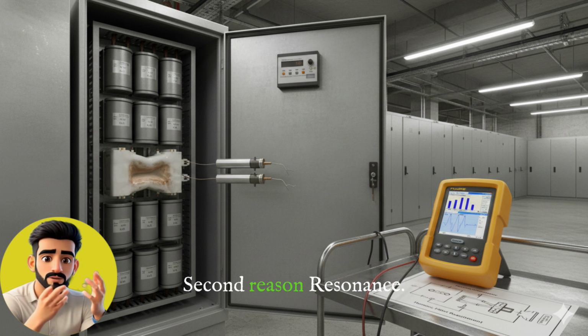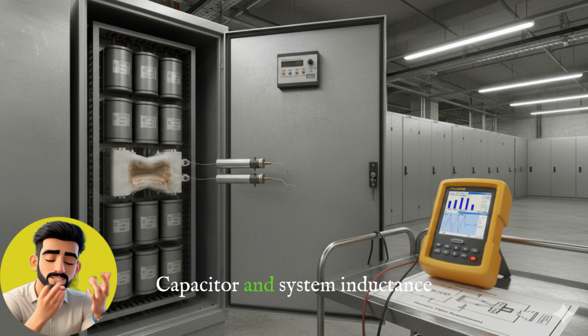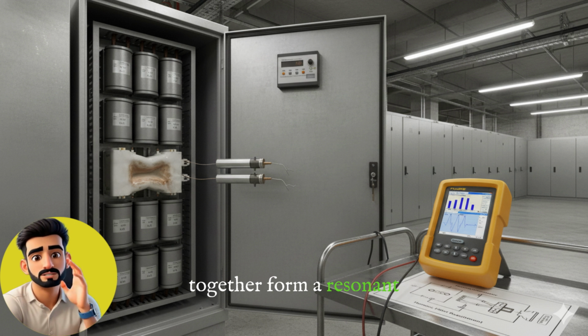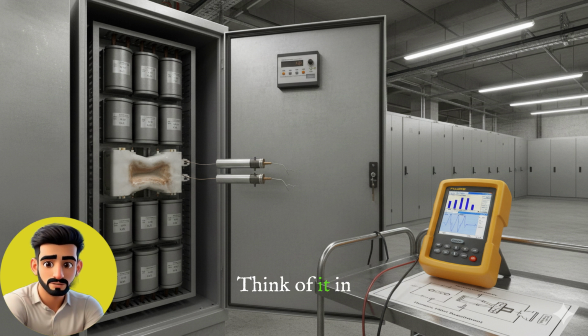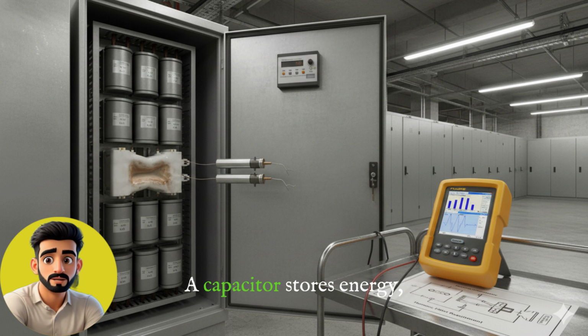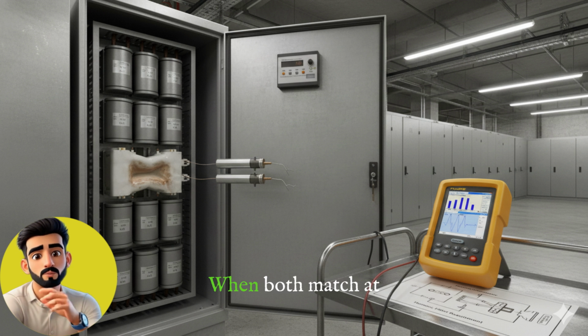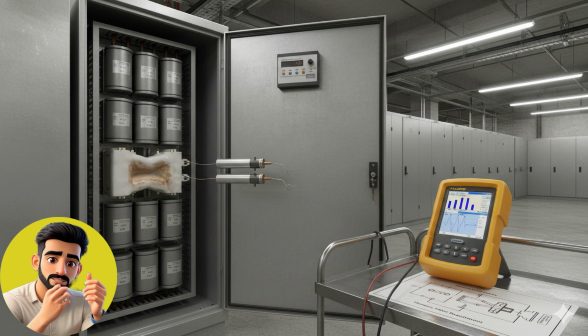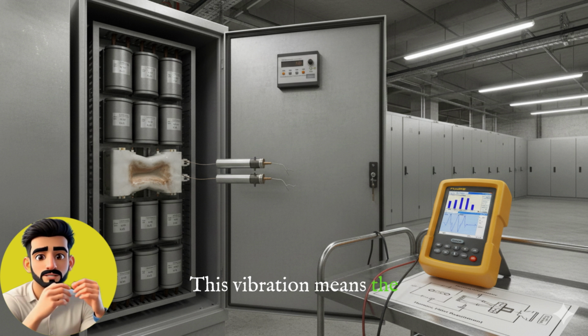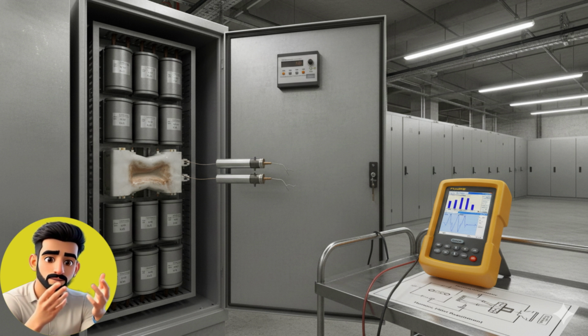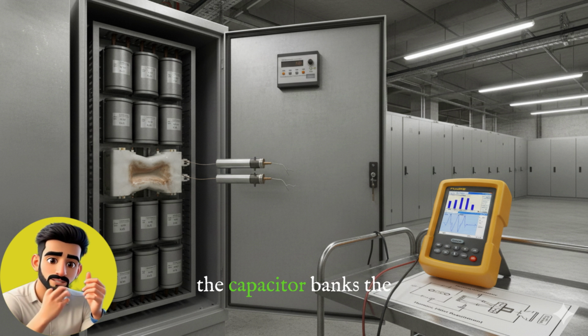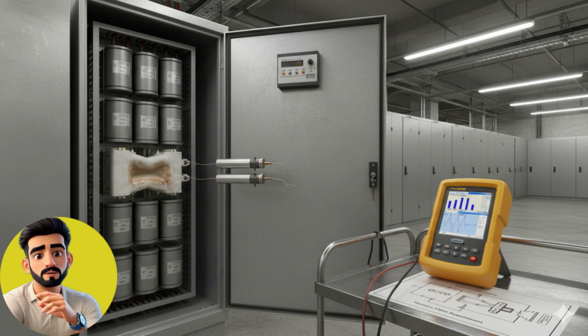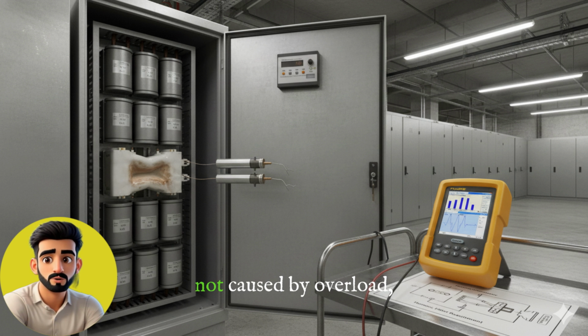Second reason, resonance. Capacitor and system inductance together form a resonant circuit. Think of it in simple language. A capacitor stores energy, an inductor stores energy. When both match at a particular harmonic, the system vibrates like a drum. This vibration means the current becomes very high. This very resonance gives the capacitor banks the most dangerous shock. Often capacitor blasts are not caused by overload, but by resonance.